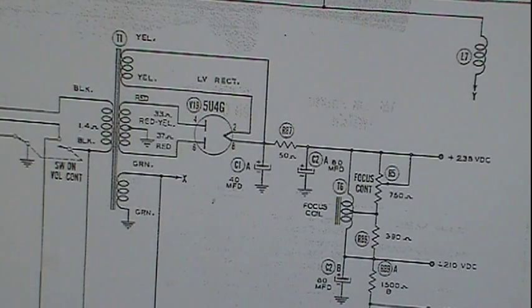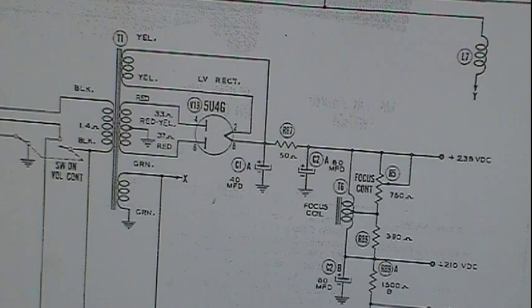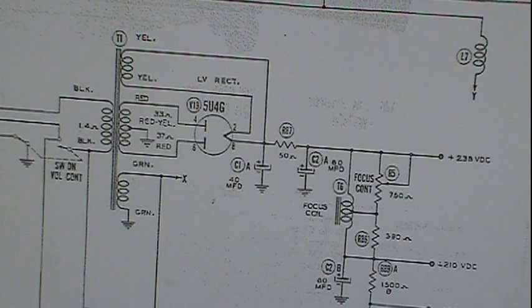It's an isolation transformer. I isolate the primary from all the secondaries because there's no connection, zero connection. The very basic isolation transformer, a simple one-to-one transformer, has a primary with a certain number of turns and a secondary with the same number of turns. They have no connection other than mutual inductance, and that's it.